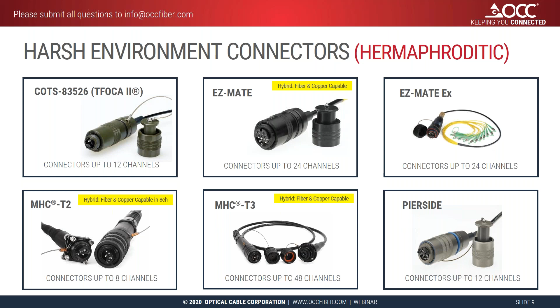Here we have our COTS 83526, often referred to as the TFOCA 2 connector in the industry. It is a hermaphroditic plug design, IP68 rated, designed to MIL spec MIL-83526/16/17 - that's where that design came from. It's been used a lot in military applications and other industries. It uses the 2.5mm termini from MIL spec 29504. Also known as TFOCA 2, it's available in 2 shell sizes: a smaller 4-channel and a larger one accommodating 12 channels. It's fully interchangeable with other manufacturers' 83526/16/17 design connectors, so it will mate up with our competitors' products.